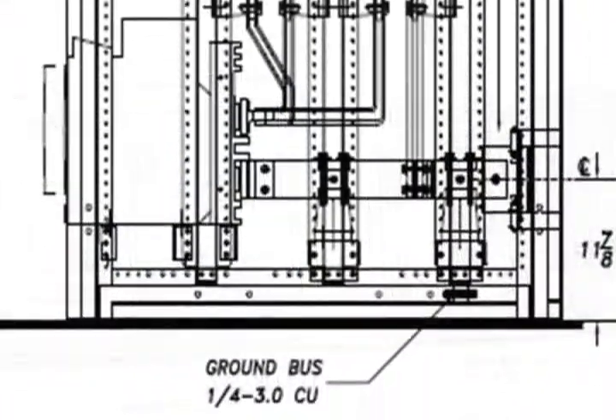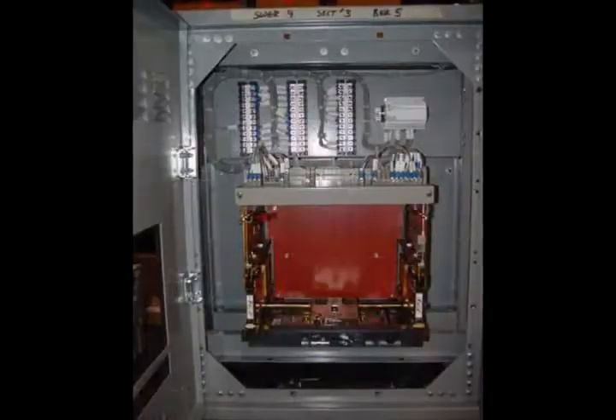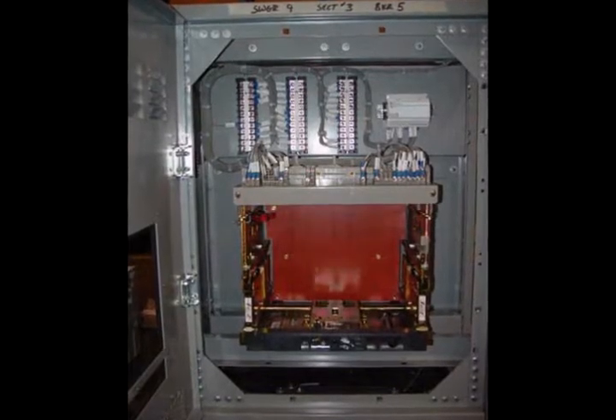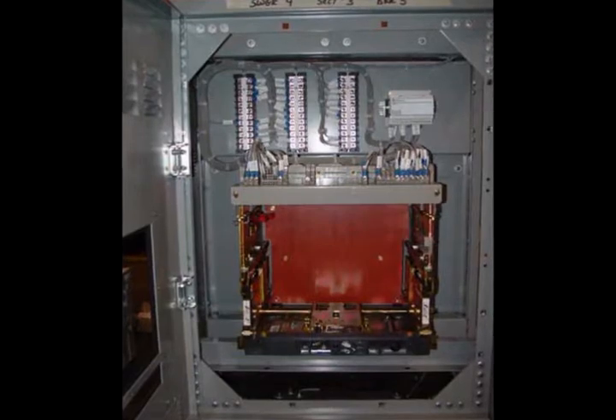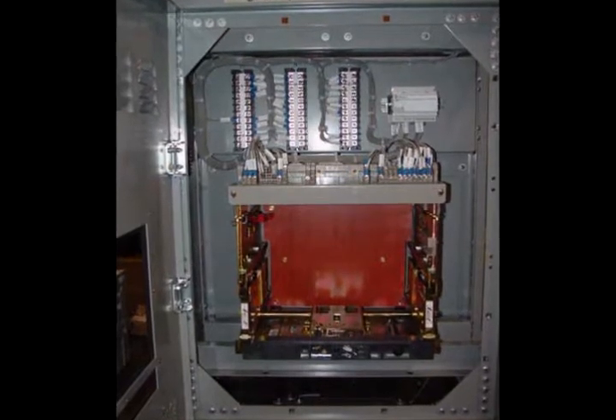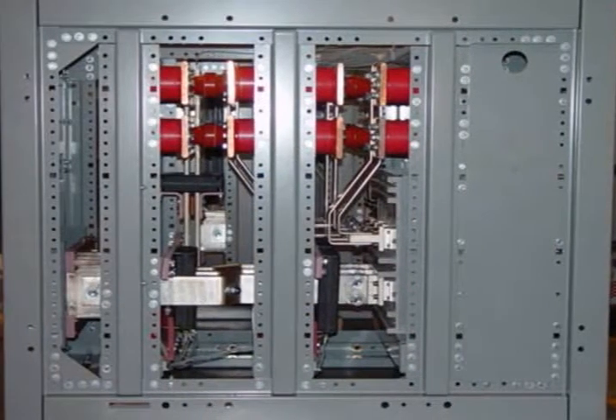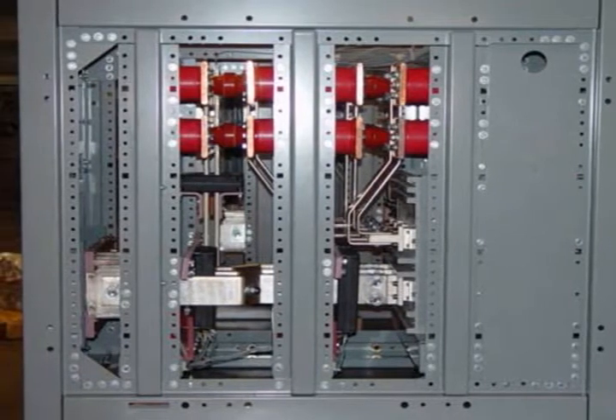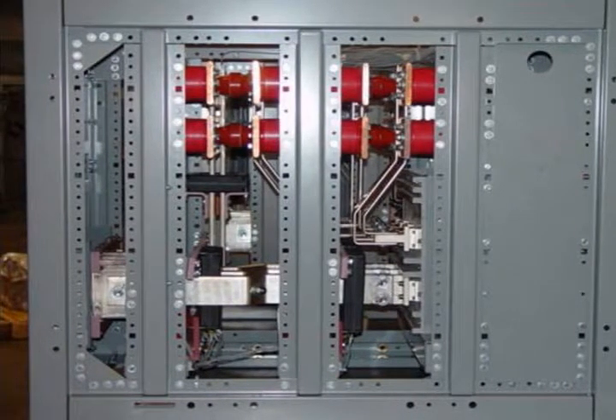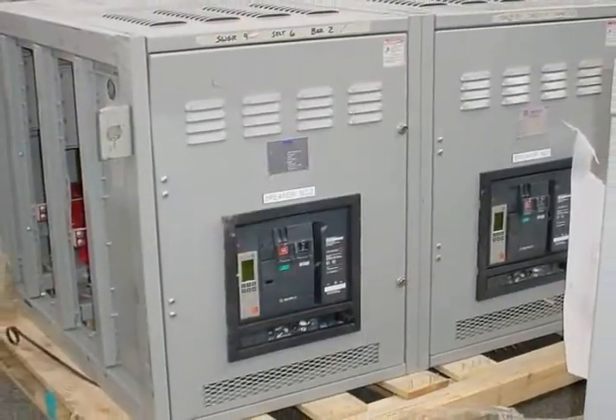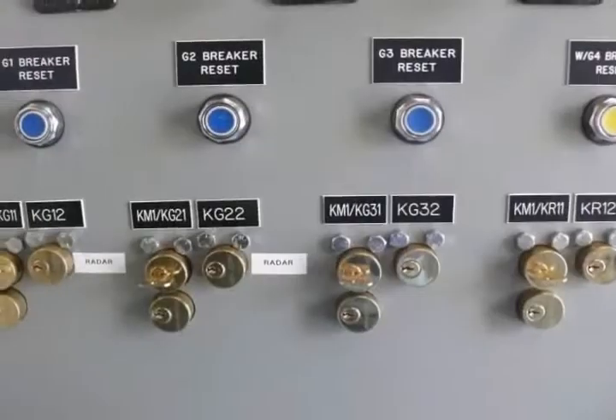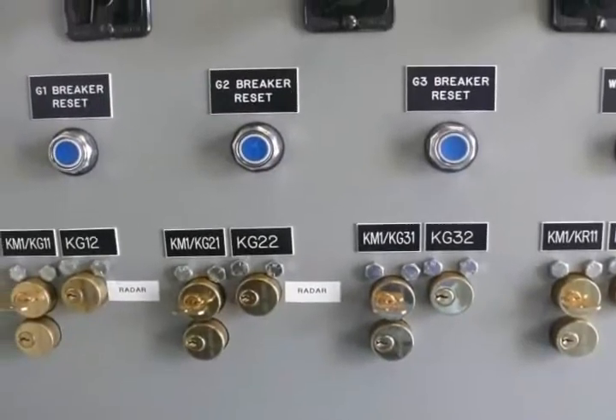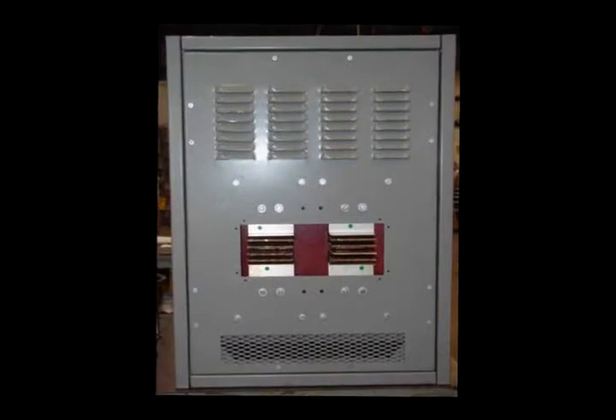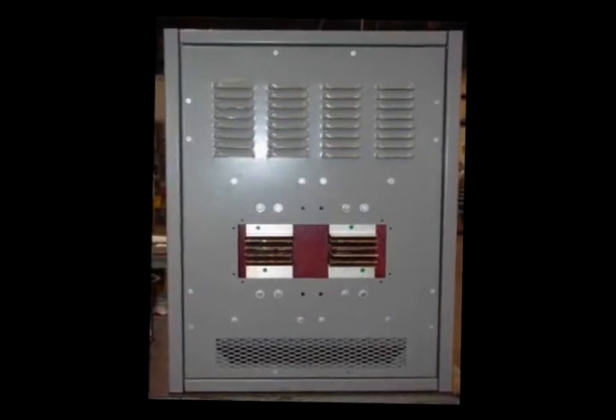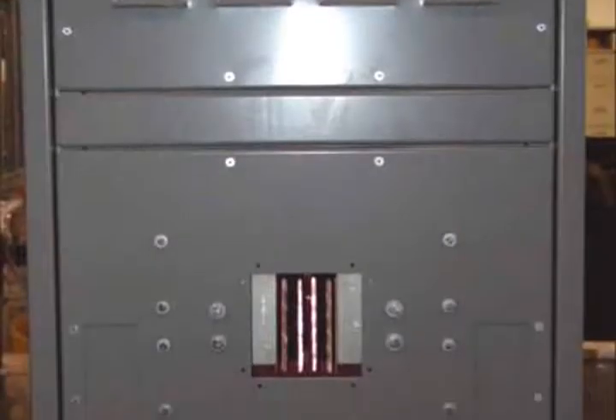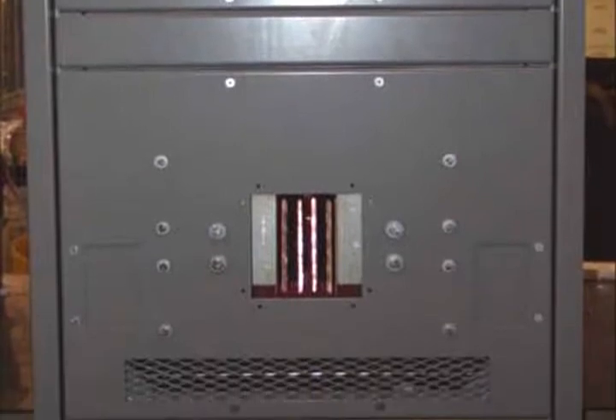Schneider Electric presented a potential solution. The customized solution was quoted to the auto plant's management, who saw immense value in not having to tear down walls. An order was placed for 40-inch high switchgear, specifically designed to fit the mezzanine. Schneider Electric Services provided two switchgear lineups with six breakers and one control cabinet. A 3,000-amp bus duct connection was included for incoming power, and outgoing feeders also had bus duct connections.